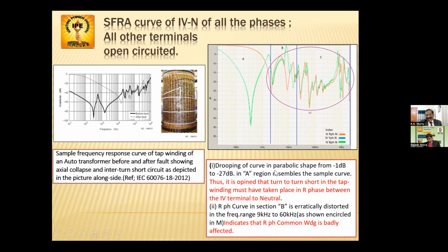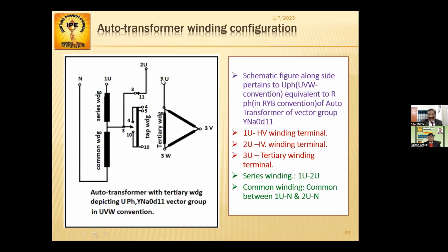Okay. So drooping of the curve in parabolic shape from 1 dB to 27 dB. This is 27 dB. So 27 dB in A region resembles the sample curve. Thus, it is my opinion that turn-to-turn short in the tap winding must have taken place in R phase between the IV terminal to neutral. This is IV terminal. IV terminal to neutral here. Here it must have taken place in this tap winding. IV terminal. It comes like this.